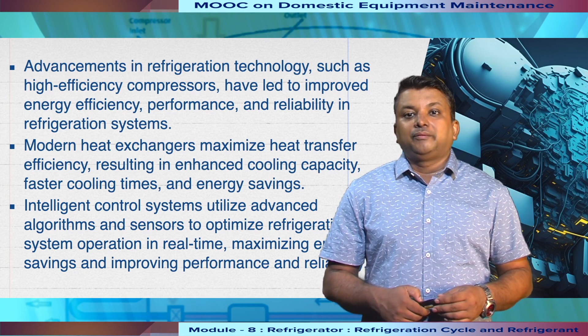One effective strategy is to use variable speed drives, or VSDs, in refrigeration systems. VSDs allow the compressor and other components to operate at variable speeds based on the required cooling load. This means the system only consumes the necessary amount of energy, resulting in significant energy savings. By adjusting the speed of the compressor and components to match cooling demands, VSDs ensure that the system operates at optimal efficiency, minimizing energy wastage and reducing environmental impact.